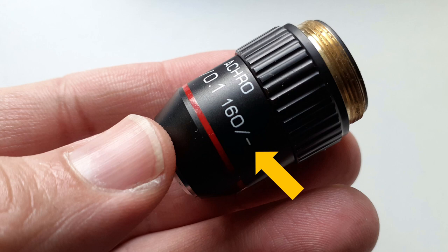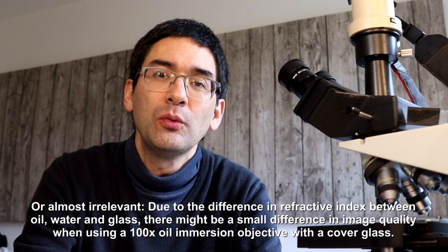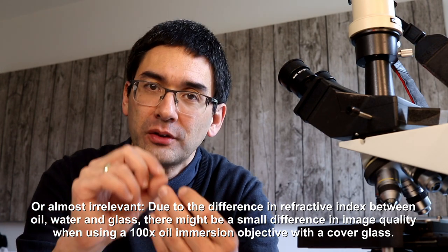There are some objectives that do not have this printed on. For example, the 4x magnifying objectives often don't have that. The reason is that cover glass thickness really doesn't make a quality difference for those objectives, and also the very high power 100x oil immersion objective often doesn't have this printed on because the effect of the cover glass becomes irrelevant when you put a drop of oil on the cover glass.